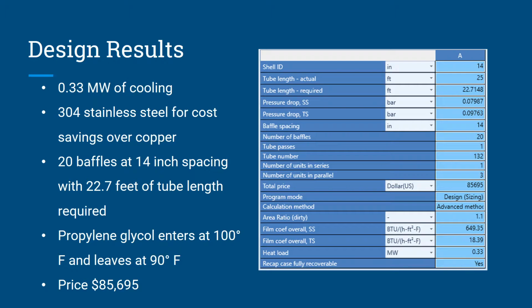The final design provided 1/3 of a megawatt of cooling for the MSU Computing Center. It is 304 stainless steel, which is cheaper than copper. There are 20 baffles at 14-inch spacing, and there is 22.7 feet of tube length required. The propylene glycol enters at 100 Fahrenheit and exits at 90 Fahrenheit. The price is approximately $86,000 with minimal maintenance required and a lifespan of several decades.